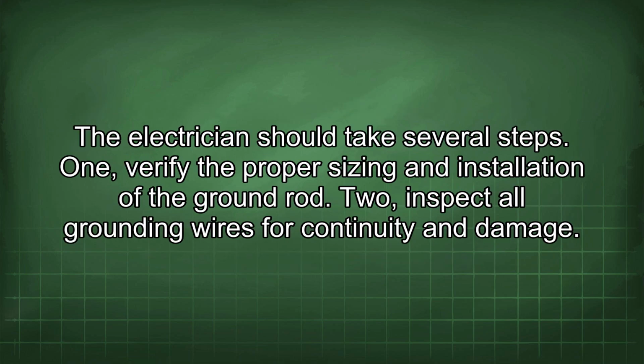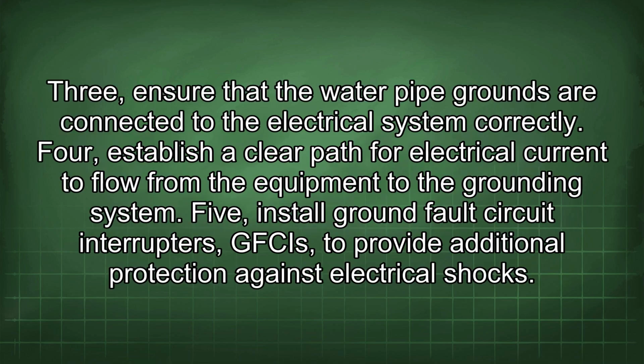The electrician should take several steps. 1. Verify the proper sizing and installation of the ground rod. 2. Inspect all grounding wires for continuity and damage. 3. Ensure that the water pipe grounds are connected to the electrical system correctly. 4. Establish a clear path for electrical current to flow from the equipment to the grounding system. 5. Install ground fault circuit interrupters, GFCIs, to provide additional protection against electrical shocks.